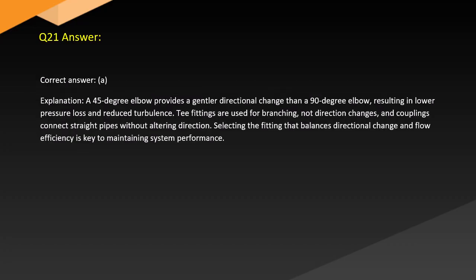Answer. Correct answer: A. Explanation. A 45-degree elbow provides a gentler directional change than a 90-degree elbow, resulting in low pressure loss and reduced turbulence. T-fittings are used for branching, not direction changes, and couplings connect straight pipes without altering direction. Selecting the fitting that balances directional change and flow efficiency is key to maintaining system performance.